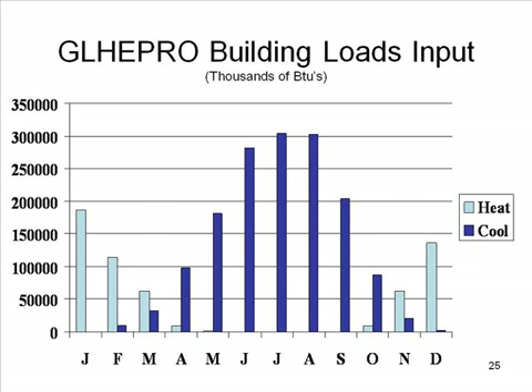Open systems are another class of system which has had a long history. I think in the southern climates, people like Florida Heat Pump probably moved down there because they had a lot of buildings and a lot of groundwater on the coastal areas, and they were pumping water through the system and then discharging it out. The open system means that someplace in that circuit, the water supply and return is going to be exposed to the atmosphere or to the ground, or it could be in a pond, could be in a vertical borehole. Very, very common. There's some very, very large systems which are open systems, and if you've got a good supply of water, it's non-corrosive, and you can discharge it.